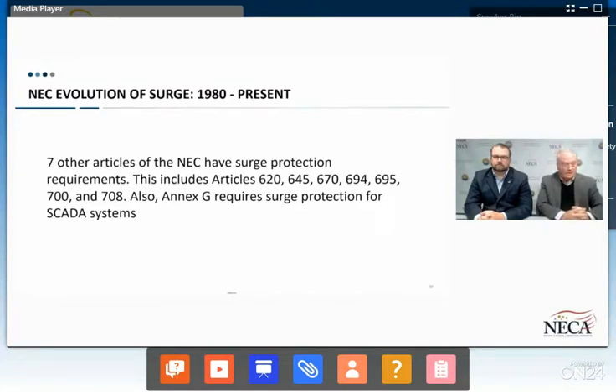And when you get into that standard, it talks about having to install surge protection for a completely installed system that has a master UL label on it. But in the 80s, in the '78 to '81 edition, the term Lightning Arrestor, as the title of Article 280, was changed to Surge Arresters. And in that article, under surge arresters, both surge protective devices and surge arresters were covered. Up until about the 2002 edition of the NEC, that's the way the code addressed it.